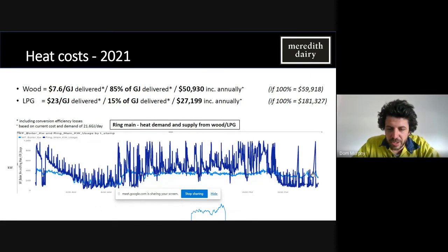I mentioned before about installing additional tanks. So now we preheat our hot water overnight. We preheat our buffer tank, which is now also increased capacity. And we run our boiler much better. We clean it more often. We make sure that our chips are dry and clean much more diligently than we did two years ago. As a result, a significant amount of the time our energy demand is met by wood chips, and the boiler just runs 24/7, never really has a break.